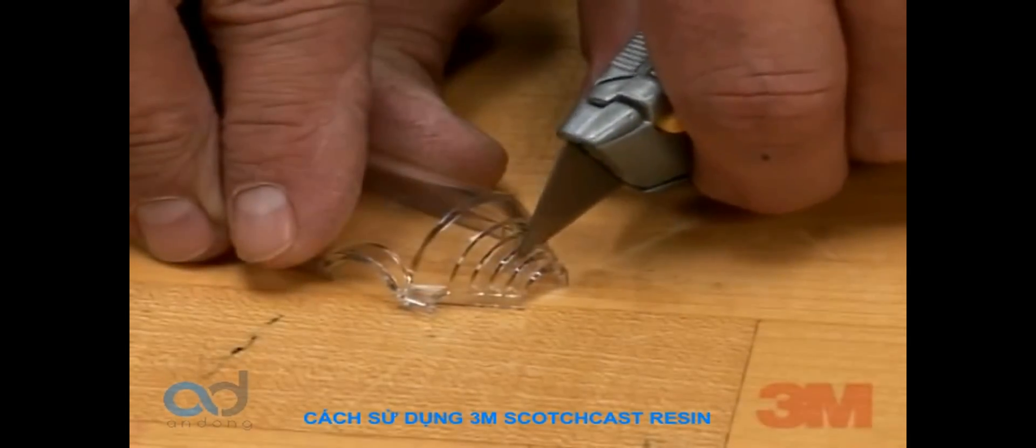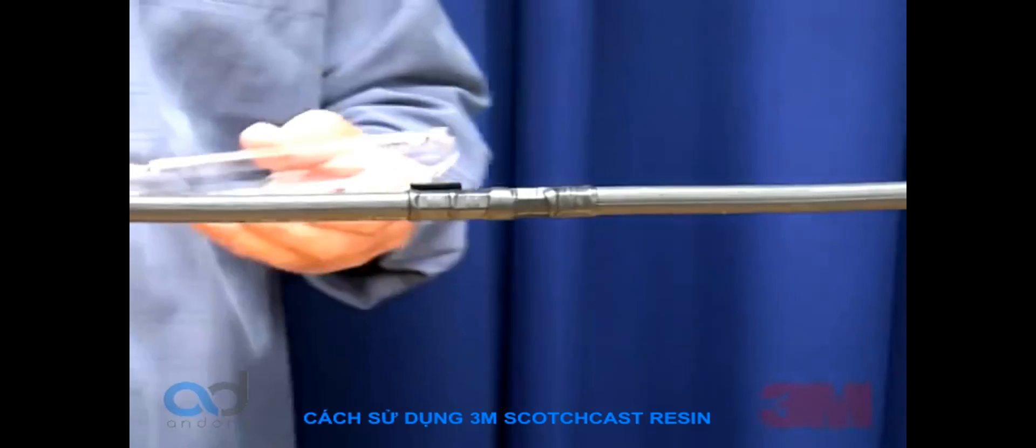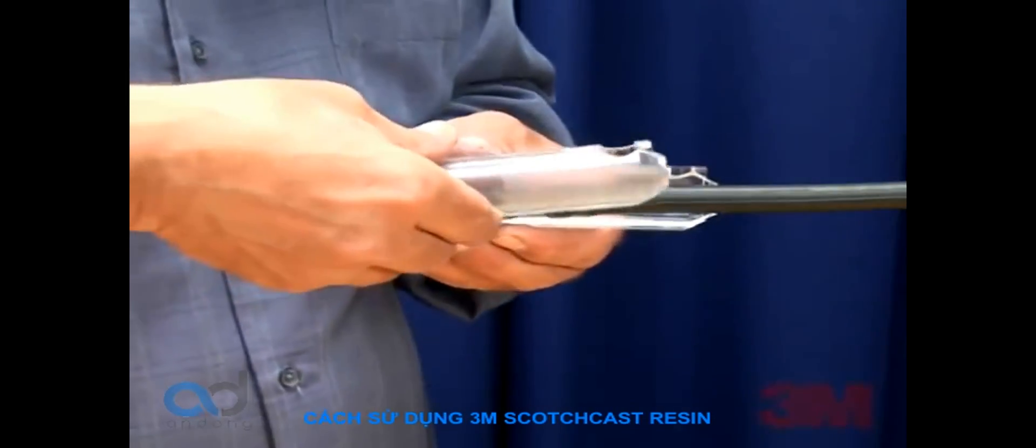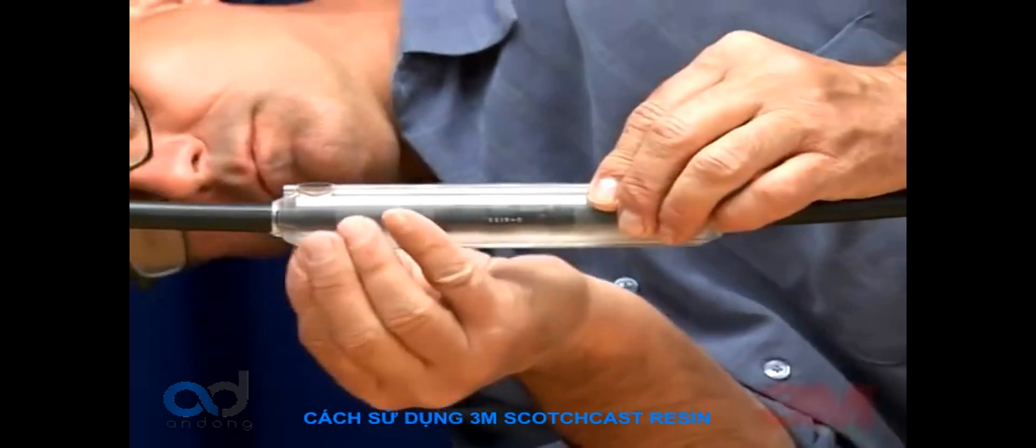Step 3: Trim the mold body ends with a blade to fit cables slightly loose. Hold the mold halves in place centered over the splice. Snap the mold halves together firmly. Check to see that both seams are carefully snapped together.